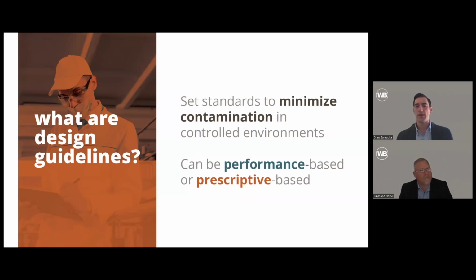Prescriptive-based is to meet a specific air change per hour, whereas performance-based is going to be based on the allowable amount of a contaminant at a particular size. So various clean room classifications will allow for more or less contaminants at different sizes of micron of contaminant.